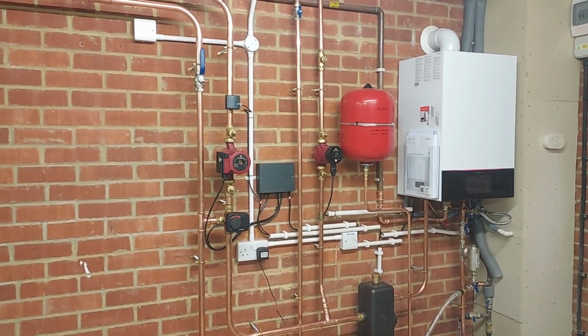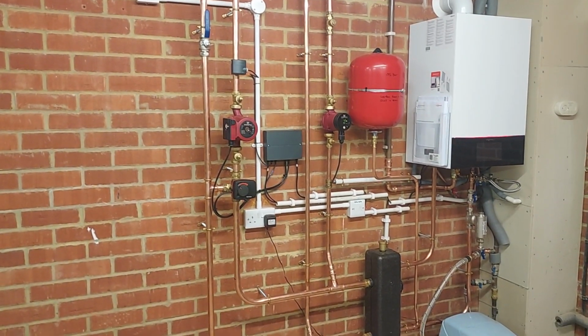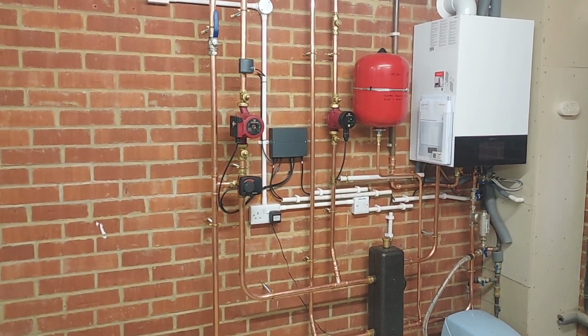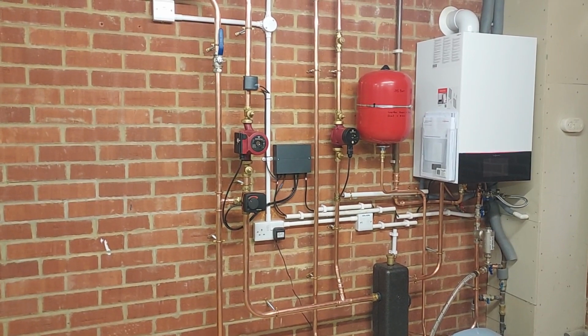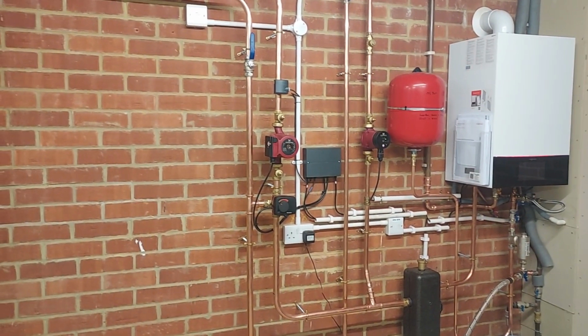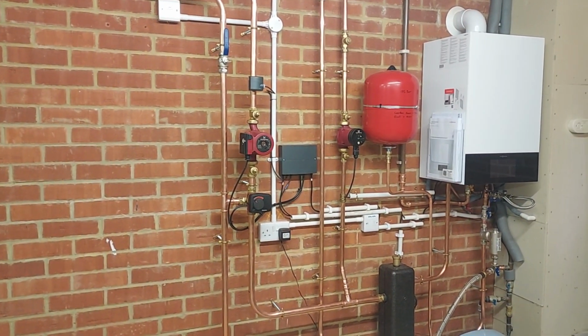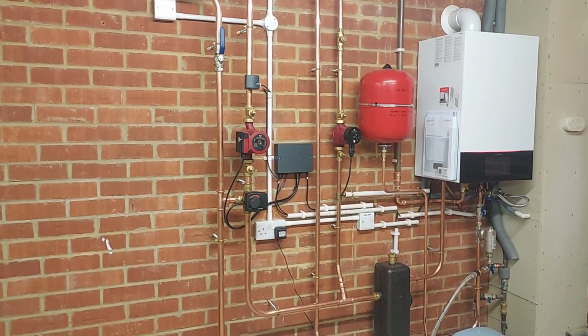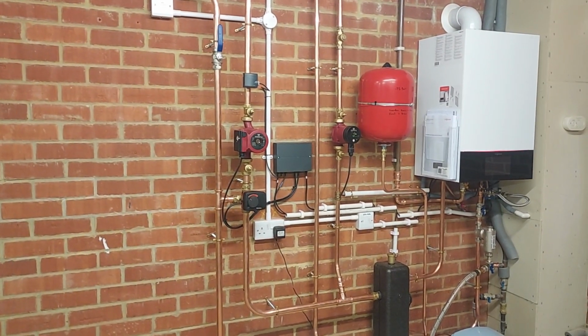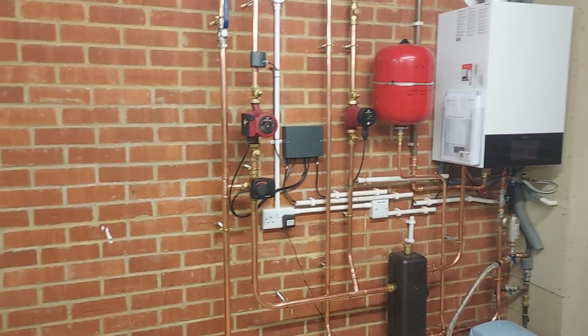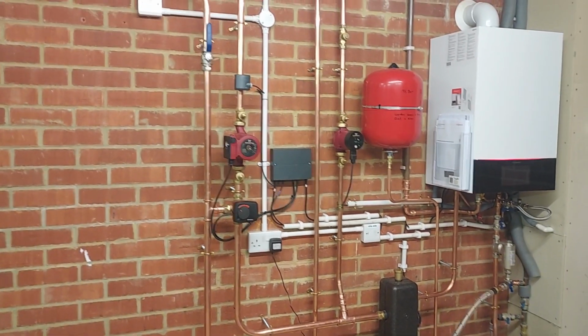Got to have 2 mixed circuits because the radiator one on the unmixed circuit is going to be running at a lower temperature than the underfloor heating circuit, although possibly we could have just put a mixer on the underfloor heating circuit. Didn't think of that one. So we could have had an unmixed underfloor and a mixed radiator circuit.